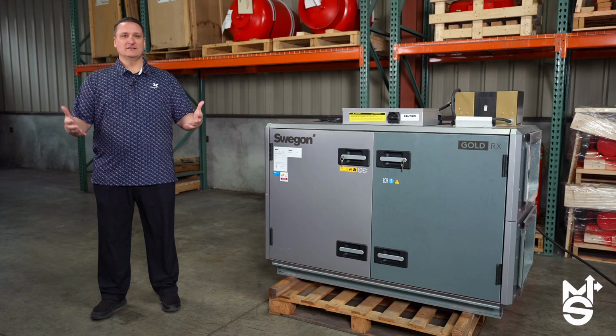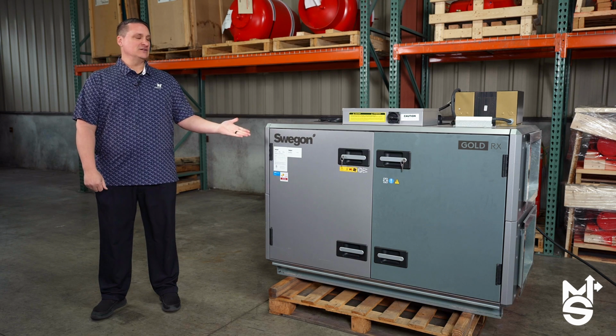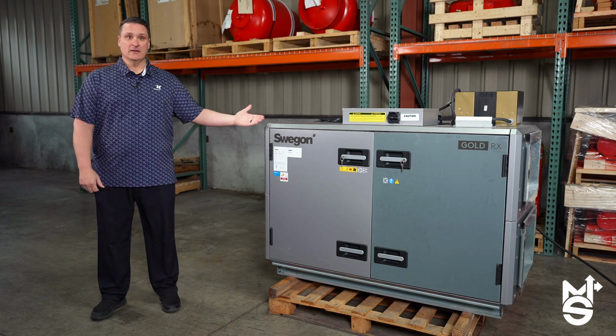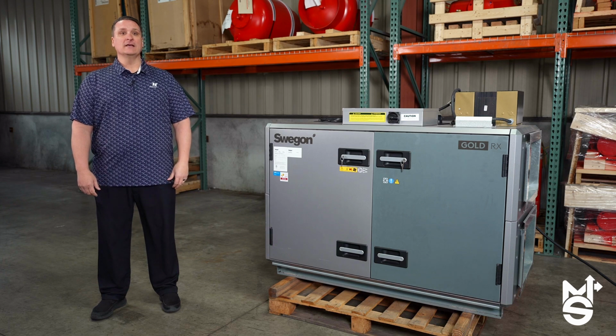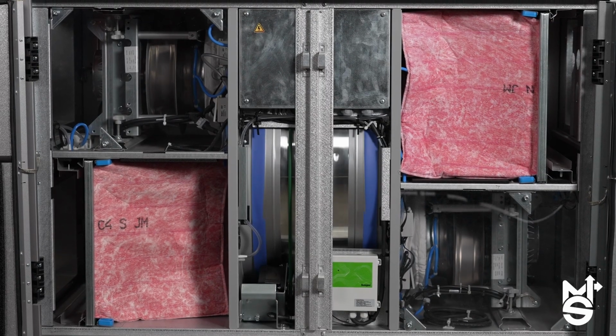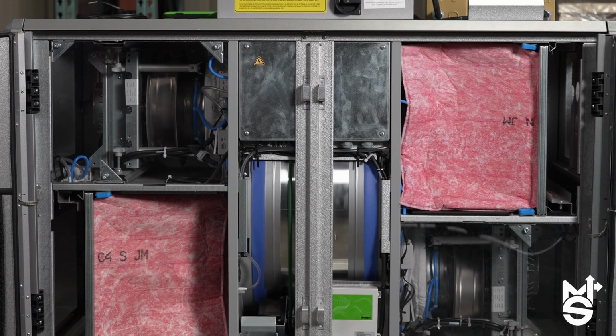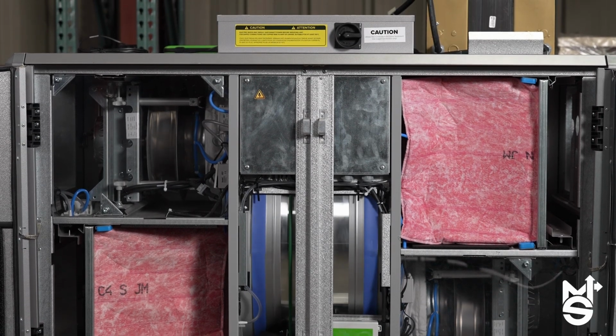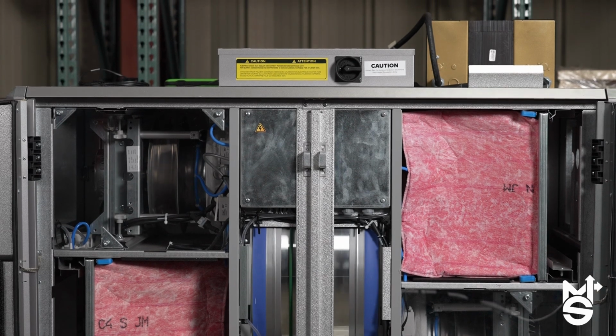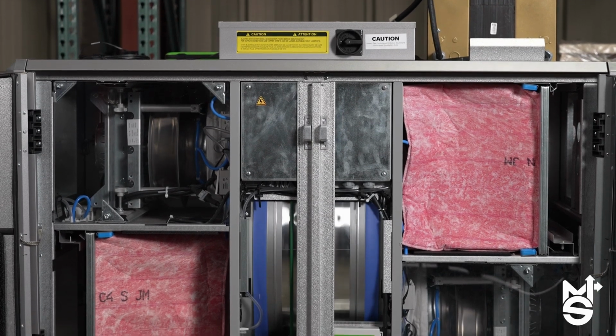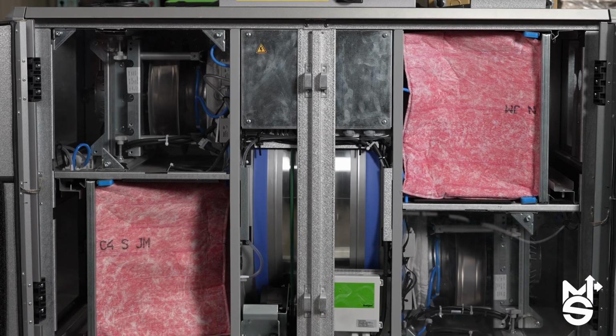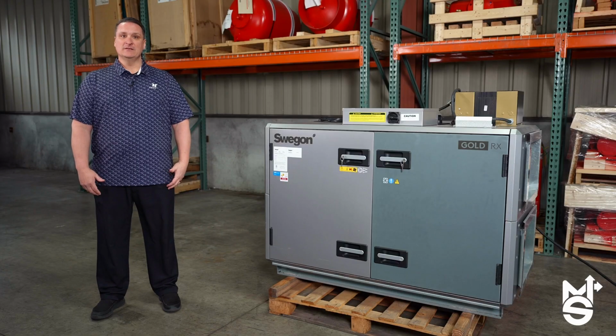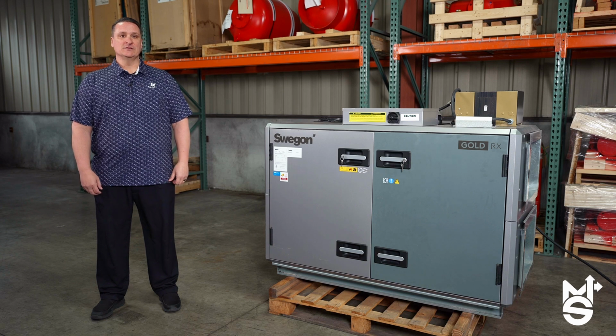What is a very high efficiency DOAS system, and what components can typically be associated with the design? DOAS starts with a very high efficiency energy recovery ventilator, known as an ERV. Example is the Swegon Gold RX ERV here. The VHE DOAS system also includes a high efficiency heating and cooling system working in conjunction with the high efficiency ERV. Example of that type of system is refrigerant-based electric heat pump delivering dedicated heating and cooling to each zone of a building. This provides ideal comfort at the individual zone level while also remaining extremely efficient.